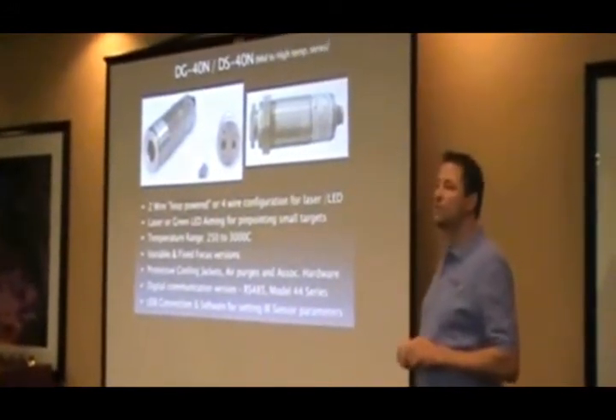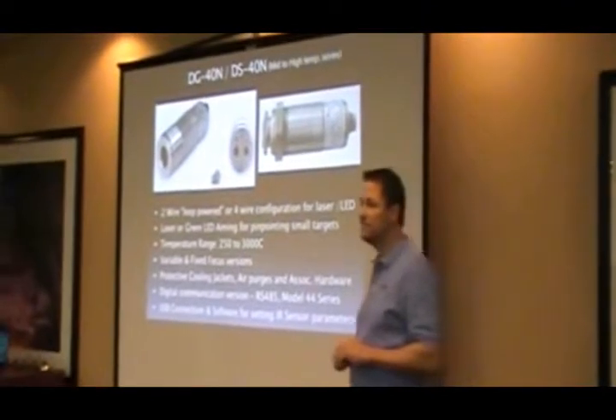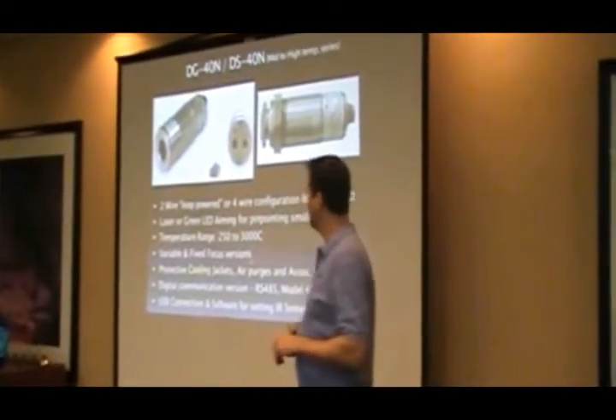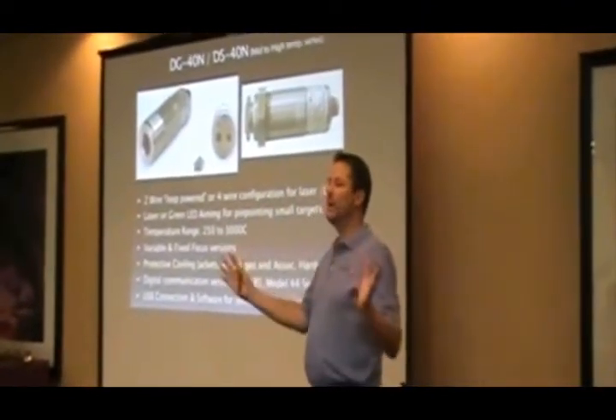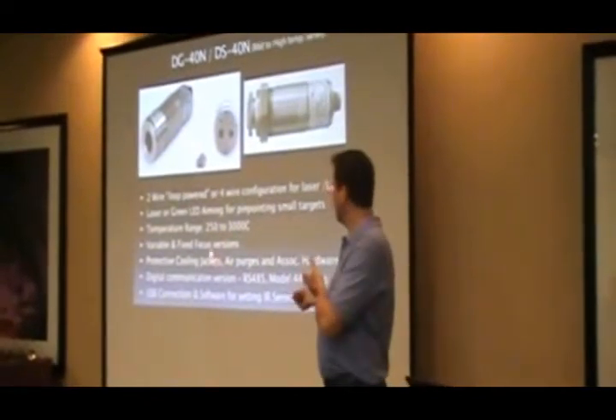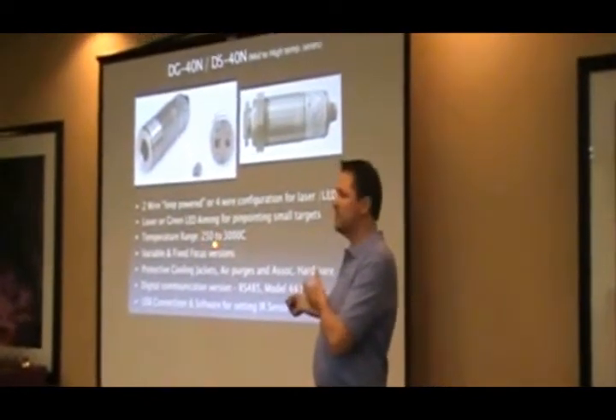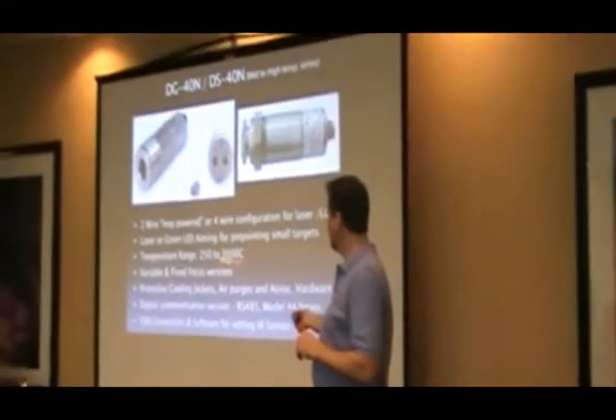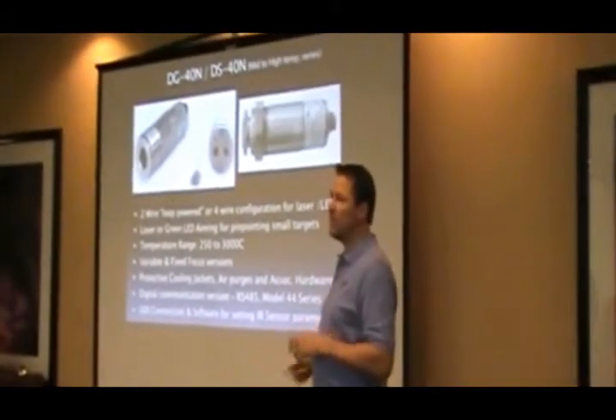Their starting temperature range is 250 degrees Celsius and goes up to 3,000 degrees Celsius. That's the whole range. So you may have to select a pyrometer from 250 to 1,000 or 1,200 C. That's the broad range of all the selections of these pyrometers.